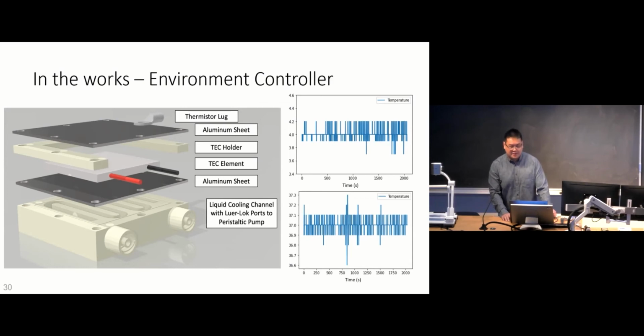This unit is capable of maintaining set point stability within a plus or minus 0.5 degrees Celsius range over 30 minutes, accommodating enough time for a complete print run. And as shown in the plots given here, there are 2 common set point temperatures displayed of 4 degrees Celsius and 37 degrees.